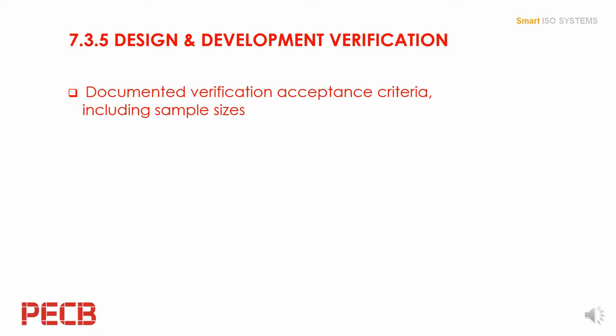On the verification activities, there is more emphasis in this clause on developing a documented process for planning the design and development verification activities. It also specifically indicates that verification plans should cover the acceptance criteria and sample sizes utilized in the design, along with the rationale behind the selection of them. If the intended use requires the device to be connected to other devices, then the design verification activities must confirm that the design outputs still meet the design inputs when connected.